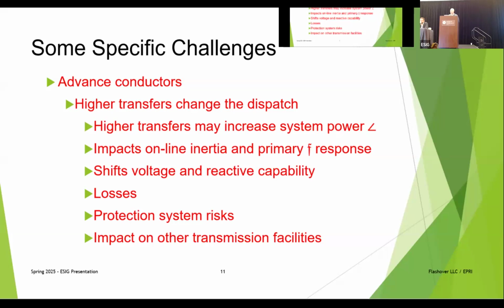Protection system risks. We're overloading a lot of equipment. Parallel circuits. I take a circuit that's 2,000 megawatts, put advanced conductor in, and I get 4,000 megawatts on it. What happens when that trips? Where do those megawatts go? So again, there's collateral damage you have to consider on other circuits, on substation equipment. God forbid you have to buy an auto transformer. That's about a 6-year wait and maybe $12 million. So just to reconductor a line with an advanced conductor, you better study everything else alongside of it.